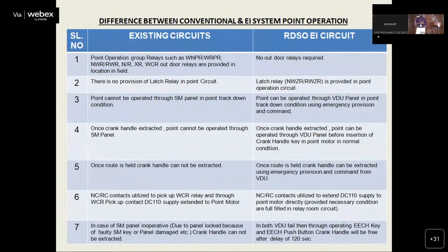Previously, in a conventional panel, if the panel was damaged or the SM key was in a damaged condition, we were not able to operate the point from the panel, and we could not extract the crank handle either; that command could not be given. But here, if both fail, an extreme emergency command is available. We rotate the extreme emergency crank handle key, reverse it, and press the extreme emergency crank handle button. After 120 seconds, all crank handles will be free, and we can extract the crank handle and operate the point.